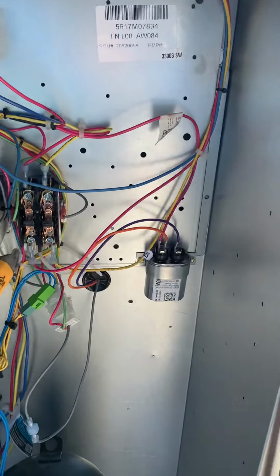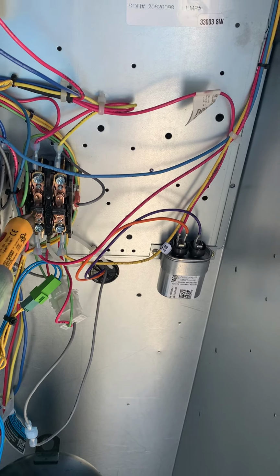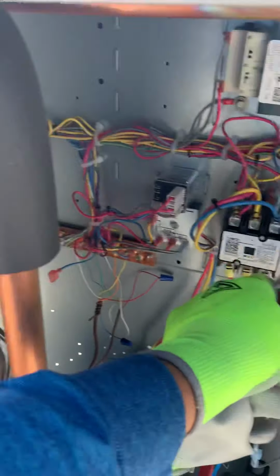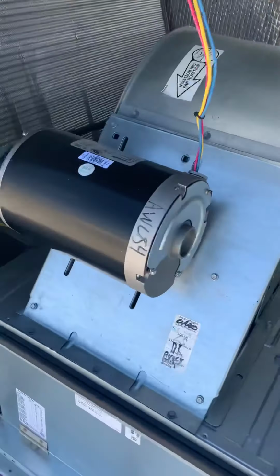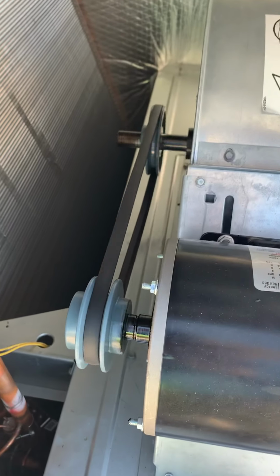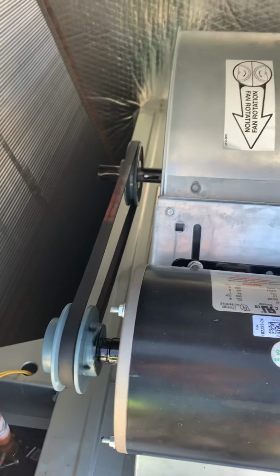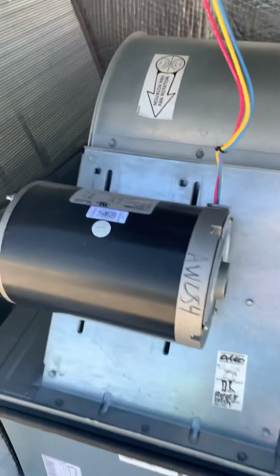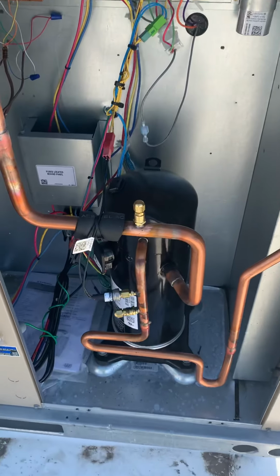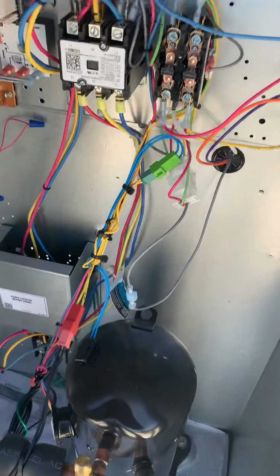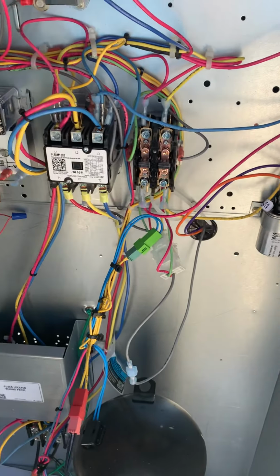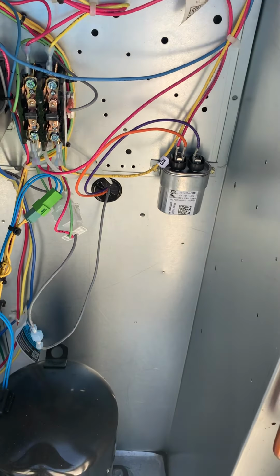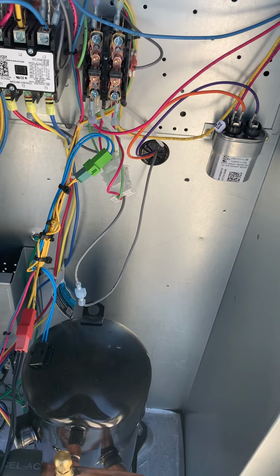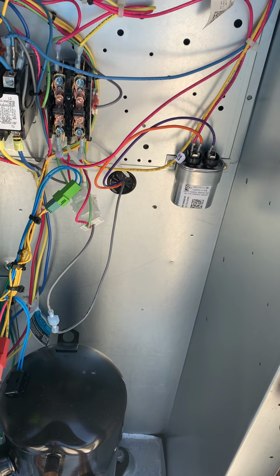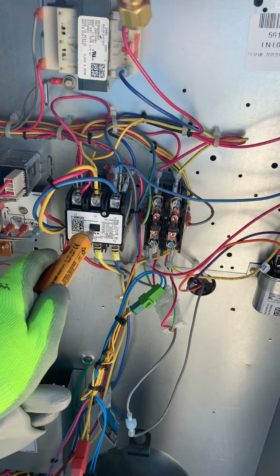So watch, when I press this contactor, it energizes the fan. You can hear it there. And now you see where the belt is running, it's running the opposite way of the arrow. That tells me the power is backwards. Another way to know is kind of playing by ear. Also the compressor tends to make a weird noise. You don't want to do that, but I'm gonna do this one.